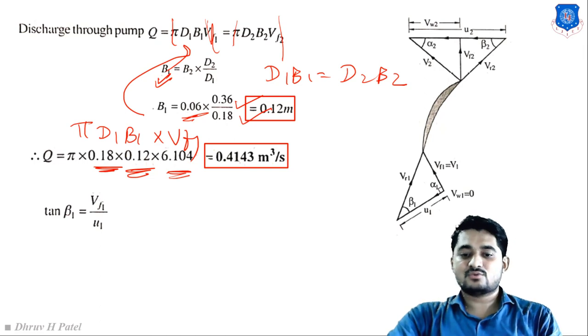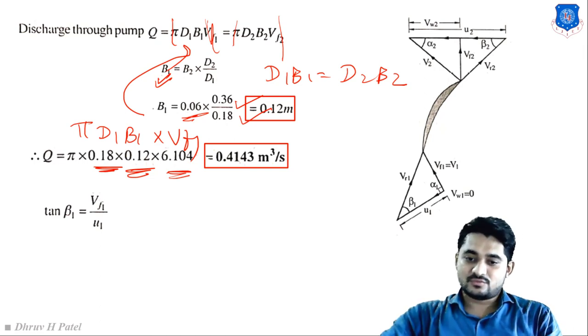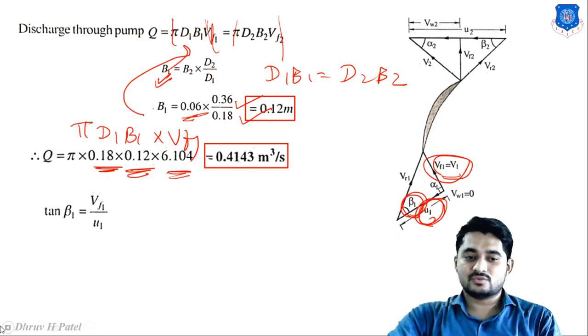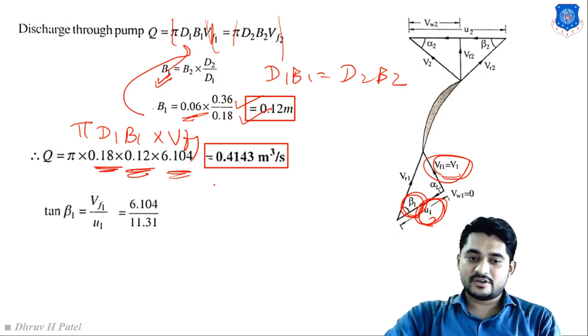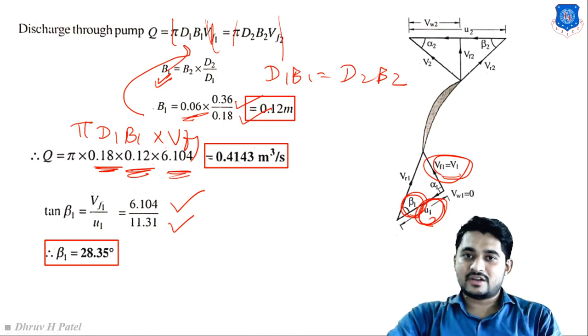Finally, we find blade angle β1 at inlet. From the inlet velocity triangle: tan β1 = V_f1 / u1 = 6.104 / 11.31. Therefore β1 = 28.35°.